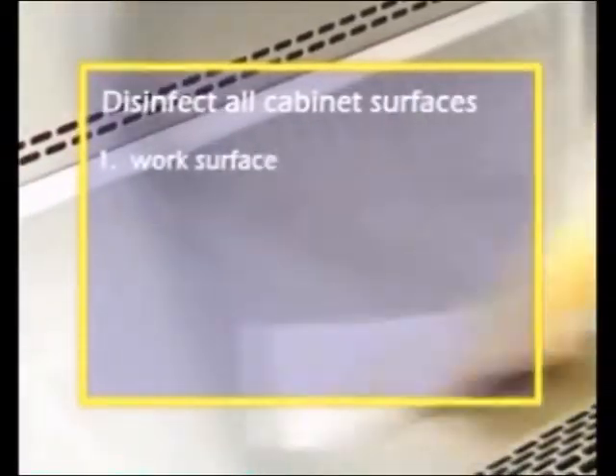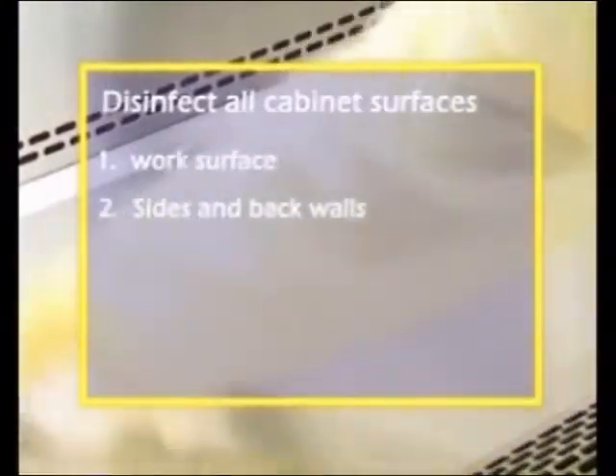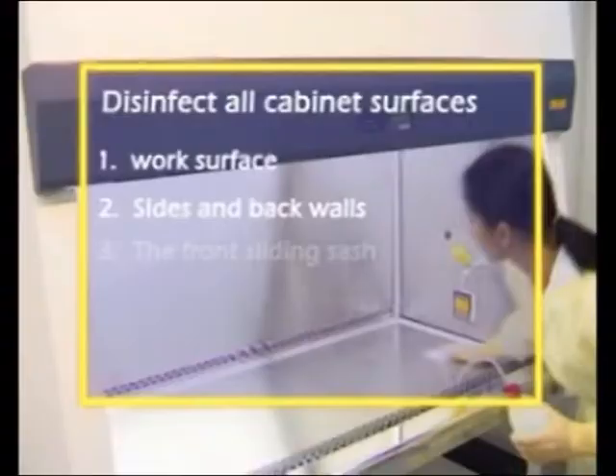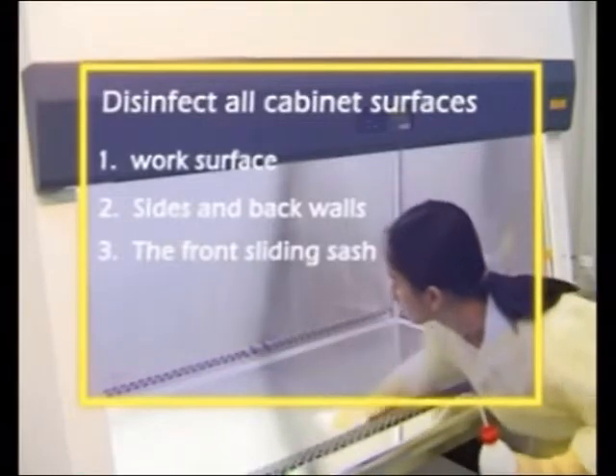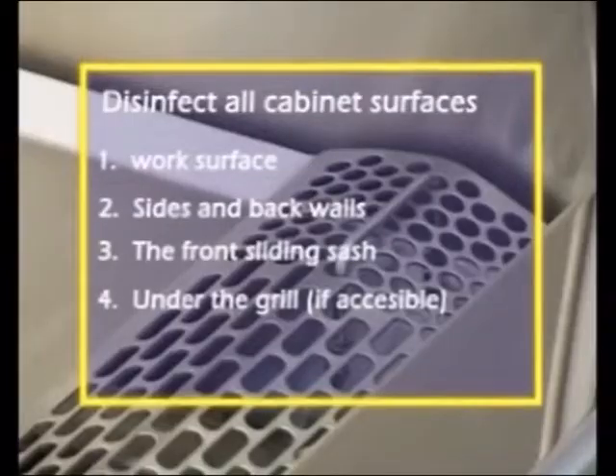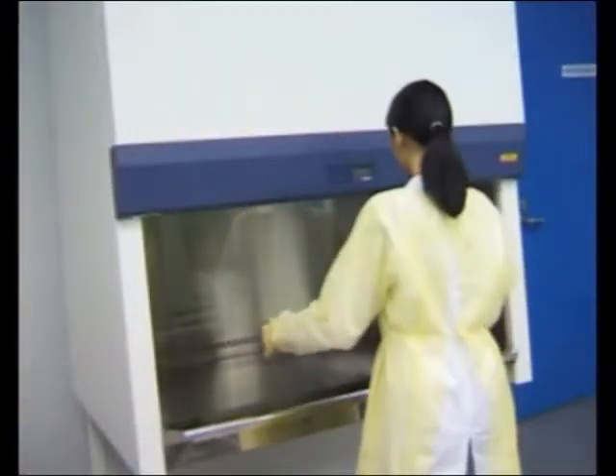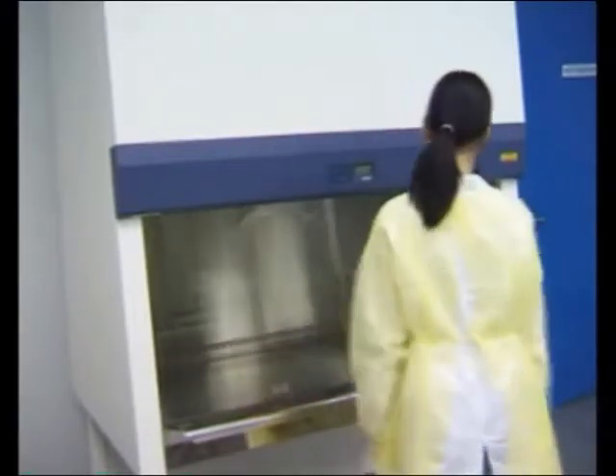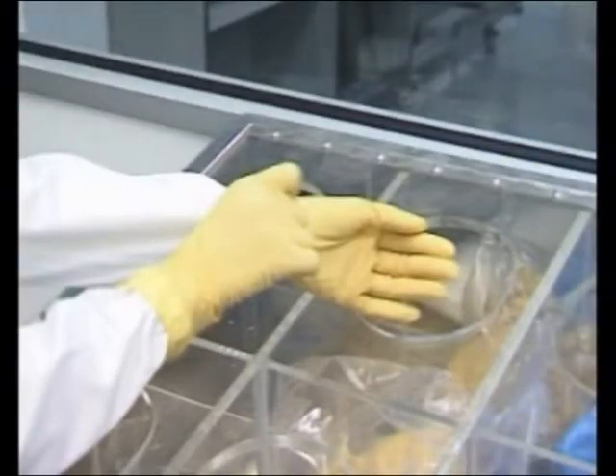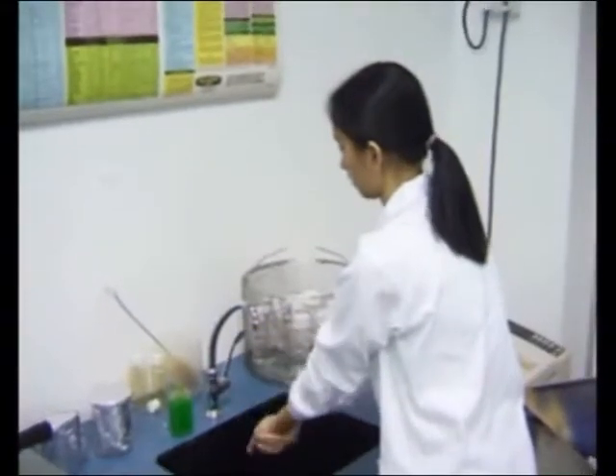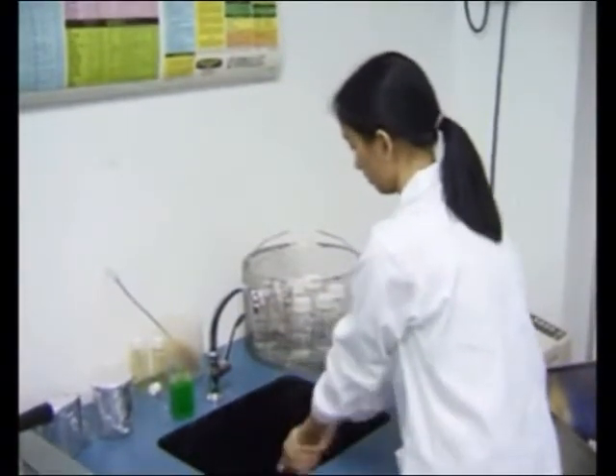Disinfect all biosafety cabinet surfaces, including the work zone side and back walls, and the front sliding sash. You should also periodically decontaminate under the front air grill. Once the biosafety cabinet is appropriately disinfected, turn off the lights, the blower, and shut the sliding sash. Degown properly by removing and disposing your gloves and removing your lab coat. Wash your hands and forearms with germicidal soap and water.